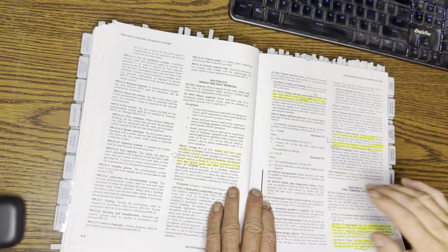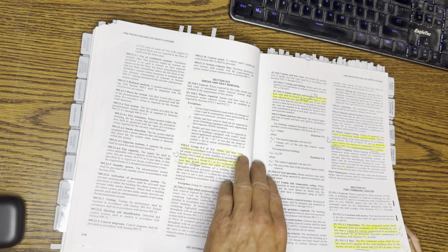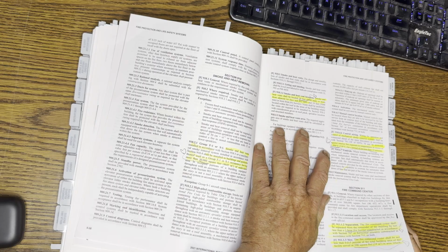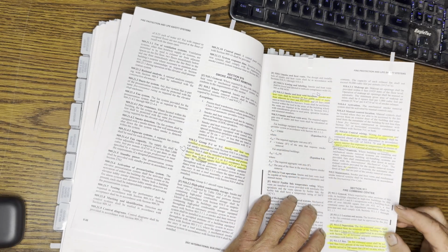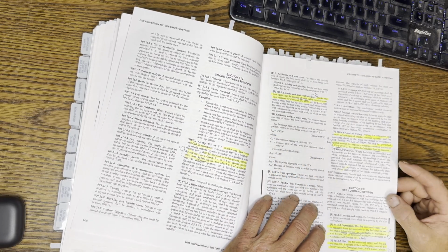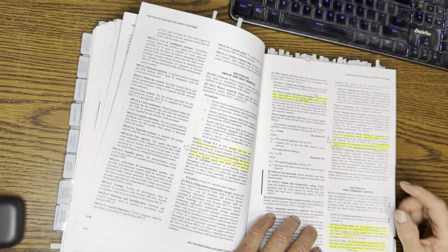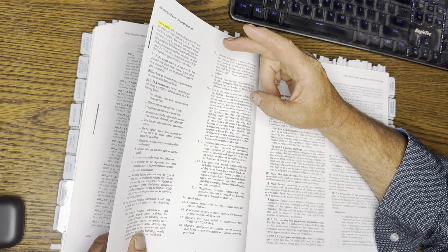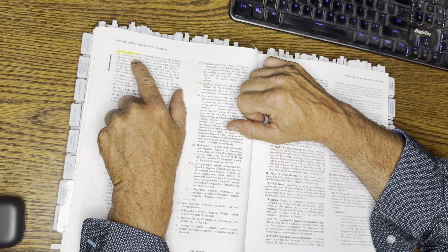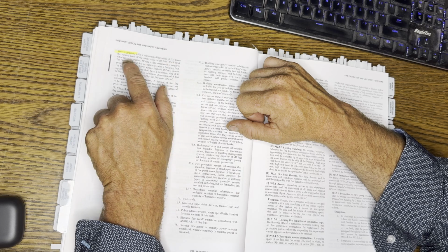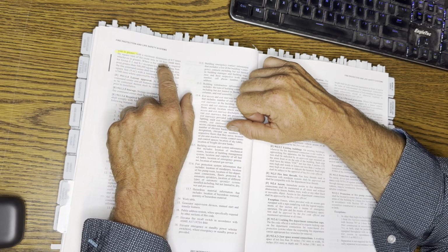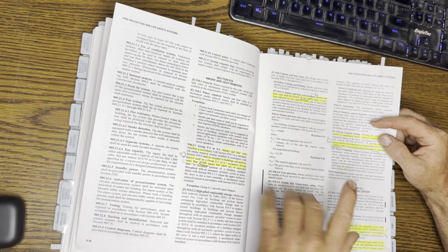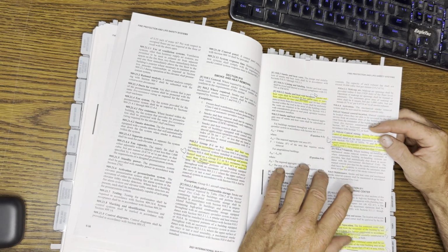Smoke and heat removal. Fire Command Center. There are some specifics in terms of size. 200 square feet comes up, and then there's another minimum dimension that comes up occasionally. It's 10 feet. So keep in mind it's 200, and high rises require fire command centers. In Chapter 4, the high-rise section, it says you need a fire command center.